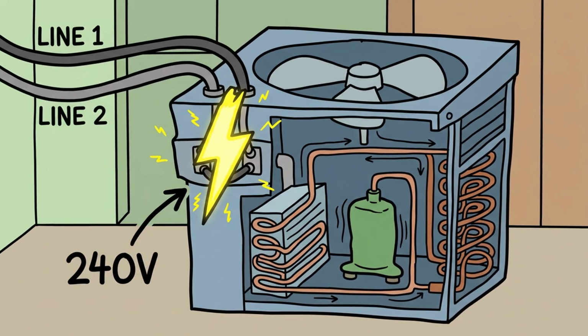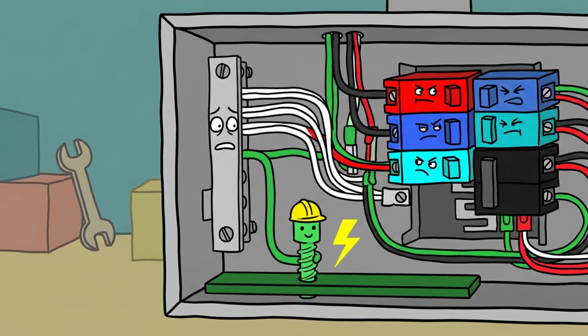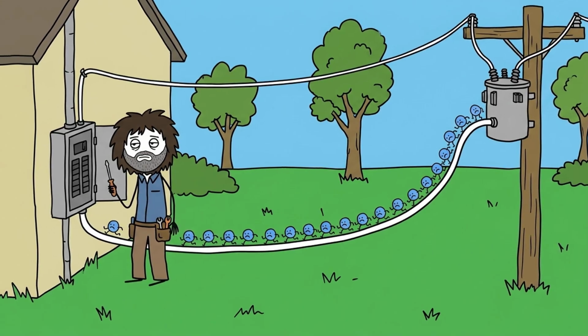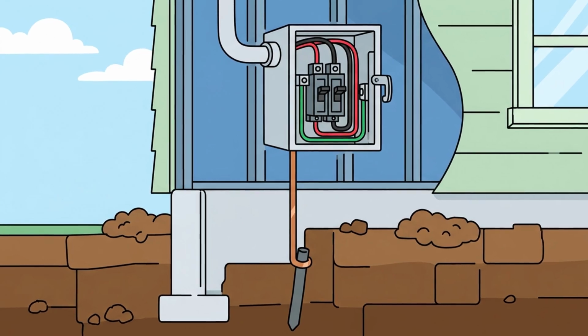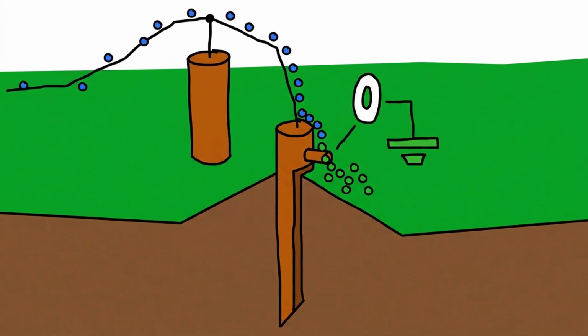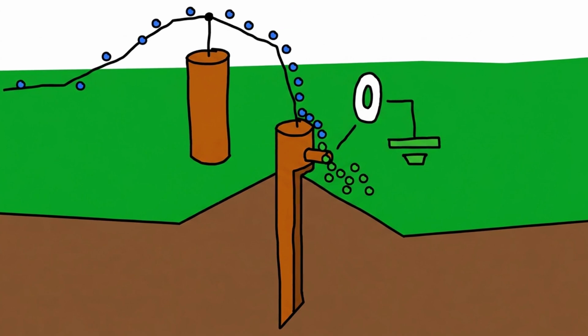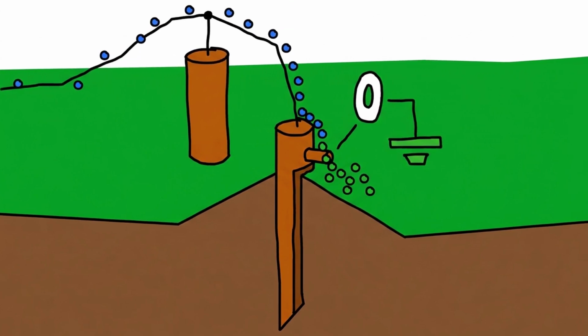An arc fault occurs when wire is pinched by a staple, chewed by a rodent, or loose behind an outlet screw. Current sputters across the air gap, generating localized temperatures over 10,000 degrees Fahrenheit without drawing enough total amperage to trip a standard thermal breaker.